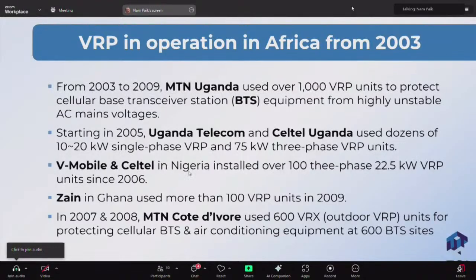V-Mobile and Celltel in Nigeria installed about 100 three-phase 22.5 kilowatt units in 2006-2007. At that time, they weren't protecting air conditioners and only needed 5 kilowatts — this was the first generation, and power requirements weren't that high. But nowadays a typical cell site might use 20 to almost 30 kilowatts, since you now have several air conditioners cooling the container and the batteries inside. More than half that load is actually air conditioner load at BTS sites nowadays.